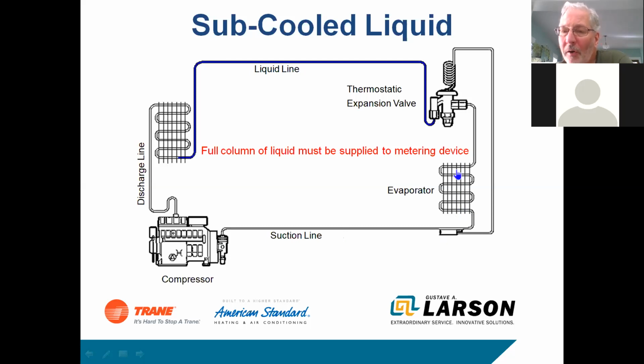If this is at 0, if we don't have any superheat here, then we have a flooded coil. When we have a flooded coil, that usually means we've got dirty filters, bad airflow, a broken belt, some issue where we're not picking up any load. We're not doing any work at that point. With an expansion valve system, you're probably not going to flood the compressor. Not a big deal. If this were a fixed orifice and we had 0 superheat here, we'd be sending liquid back to the compressor, which would be a really not good situation.